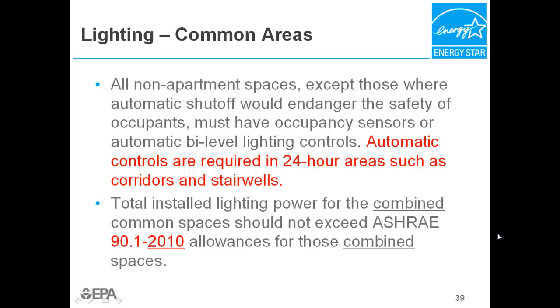These common spaces are also subject to a prescriptive requirement that limits the amount of lighting installed. The total installed lighting power for the combined common spaces should not exceed ASHRAE 90.1/2010 allowances for those combined spaces. The performance path allowed an excess of up to 20% over 90.1/2007. This is not permitted in the prescriptive path.